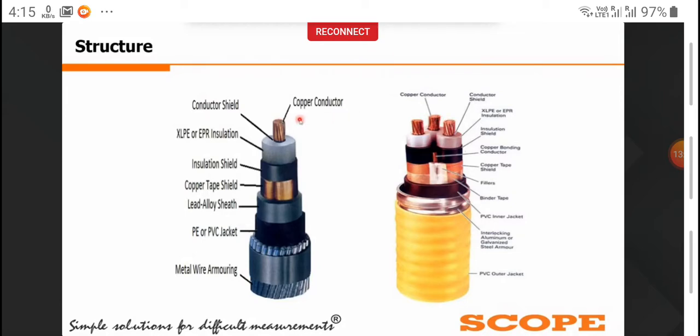In electrical equivalence, aluminum requires 1.6 times the cross-sectional area of copper, though at half the weight.